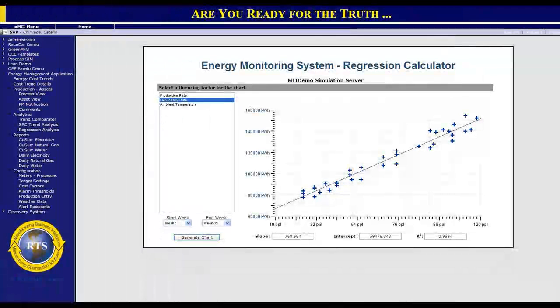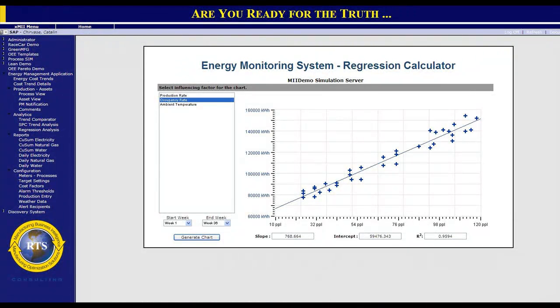The next screen displays linear regression analysis. By plotting a series of energy usage parameters with tonnage of production to be correlated, it enables quick identification of energy anomalies. We can obtain energy target baselines dependent on production volume, and a multitude of independent parameters may be selected for the regression analysis.